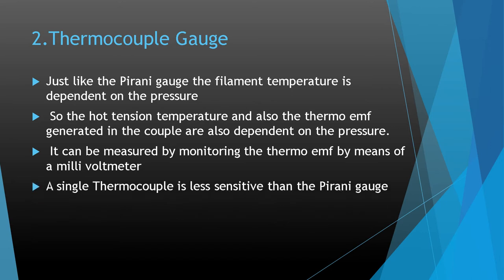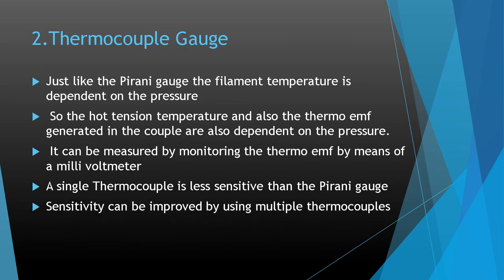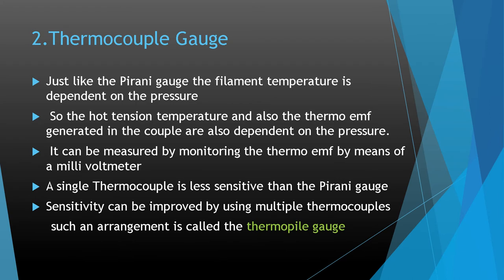A single thermocouple is less sensitive than a Pirani gauge. Sensitivity can be improved by using multiple thermocouples. Such an arrangement is called a thermo-pile gauge.